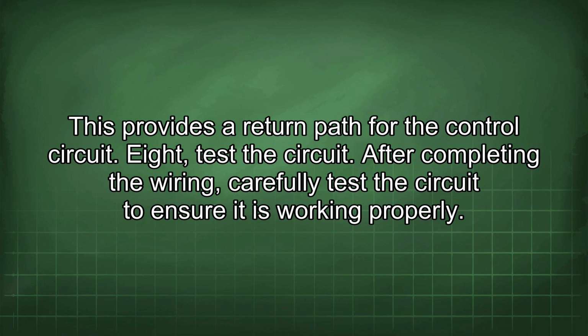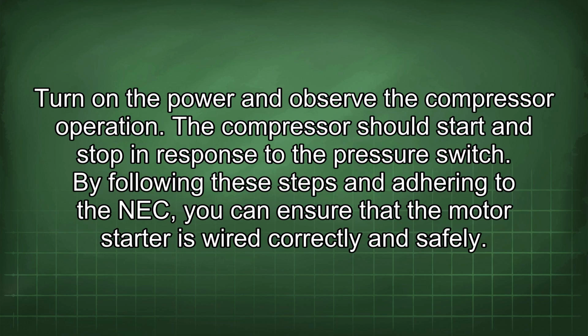8. Test the circuit. After completing the wiring, carefully test the circuit to ensure it is working properly. Turn on the power and observe the compressor operation. The compressor should start and stop in response to the pressure switch.